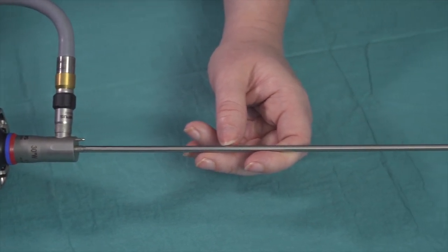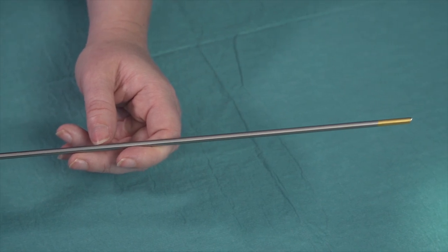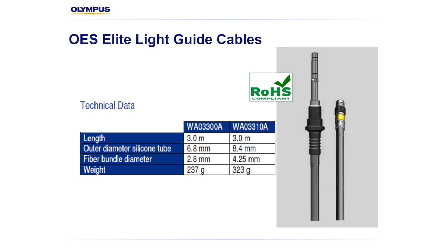Light continues to travel along the telescope illuminating the optics, and finally the light is emitted at the lens. Depending on the diameter of the telescope you are using, you may want to use a smaller or larger light guide. Olympus sells two sizes of light guide: small and medium. The smaller light guide is suited to smaller diameter telescopes such as those used in urology with a four millimetre diameter, ensuring the light post of the telescope does not overheat and cause unnecessary heat-related wear to the telescope components.